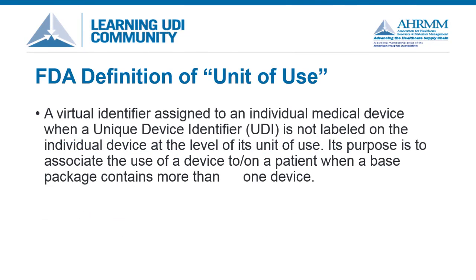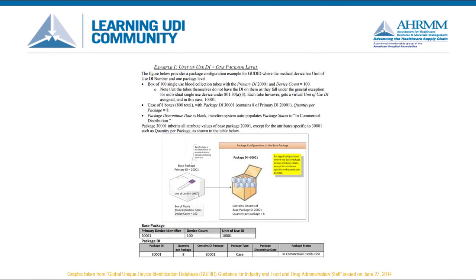The language on this slide is taken directly from the FDA documents creating the Unique Device Identification Program. It states that when the lowest packaged level of a product contains more than one device, an unmarked Unit of Use Identifier should be created. This graphic is taken from an FDA guidance document released in June 2014, and describes the correct application of the Unit of Use Identifier as originally conceived by the FDA.